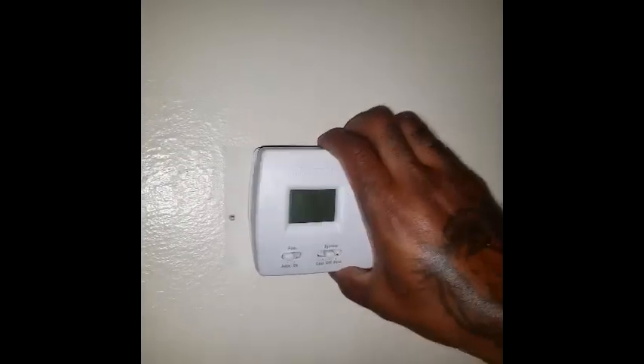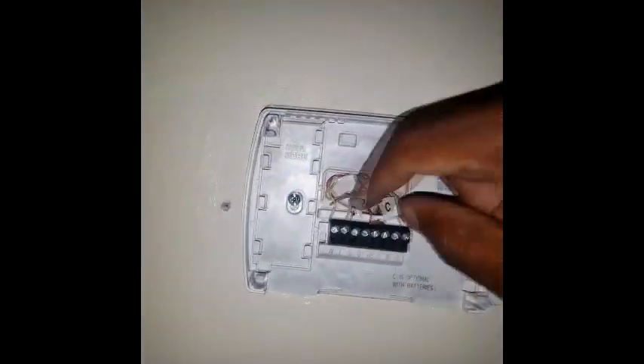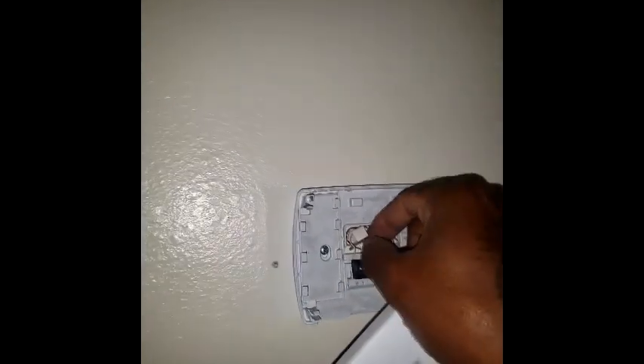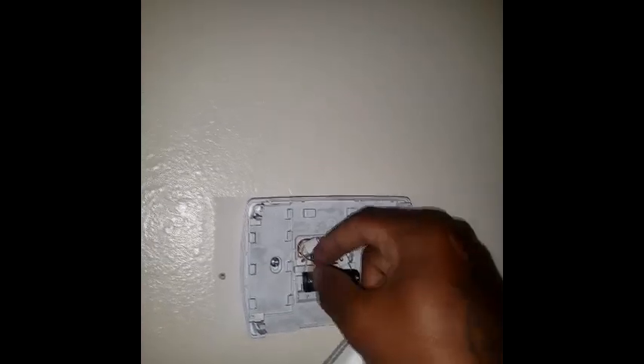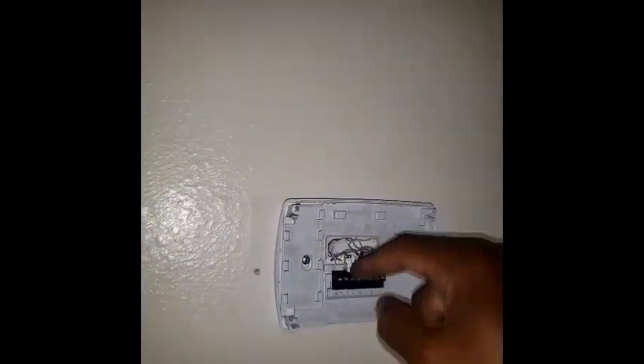Like I say, it'll work in cool mode. I can take the thermostat off the wall, I already have my meter to check voltage at the control. Even with the unit off, you can take this green wire off right here and go to the controller, and I don't know if you can hear it, but that fan is still on.